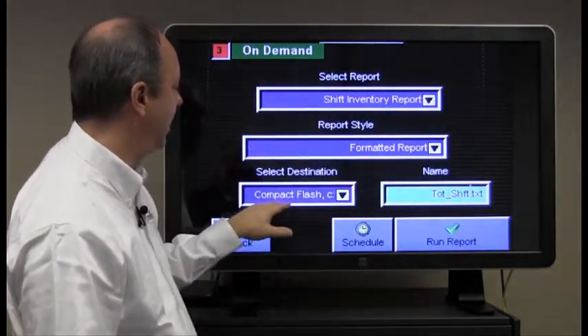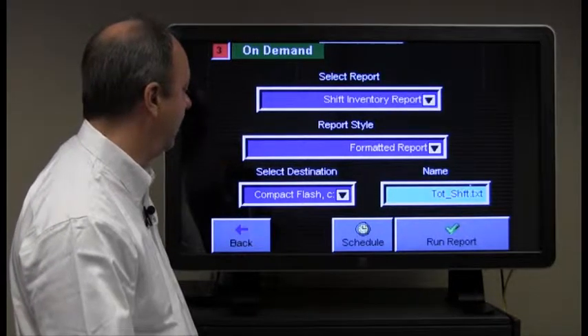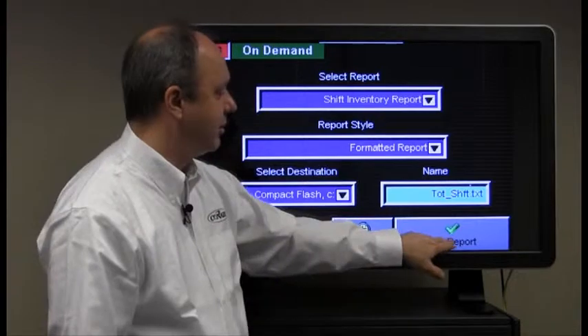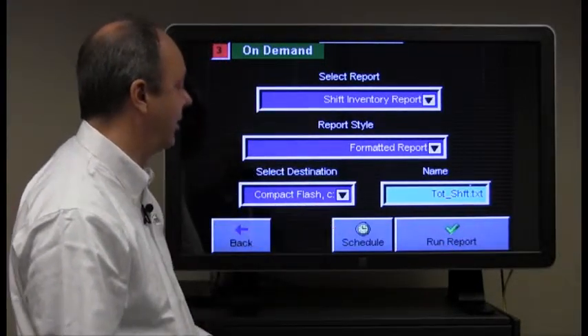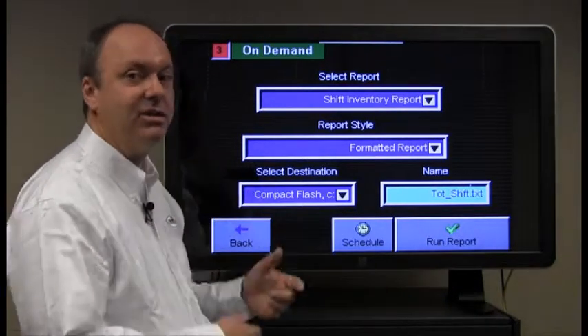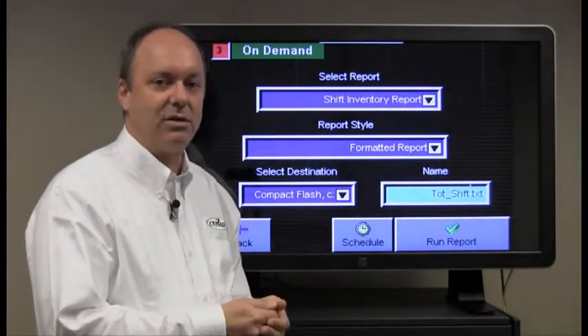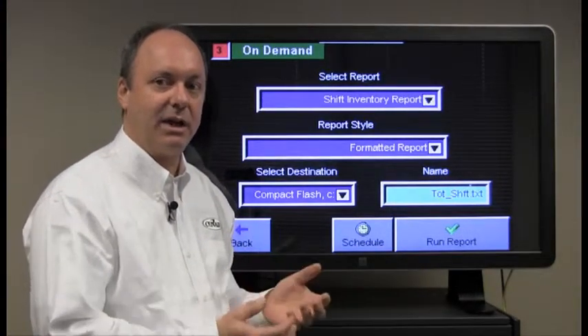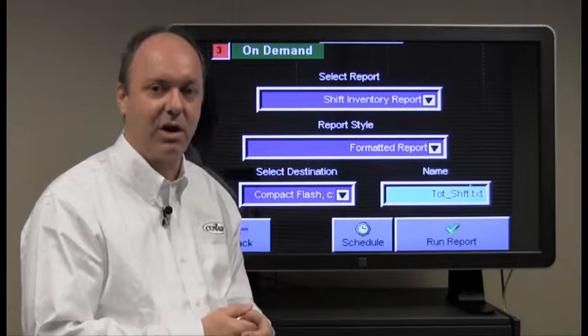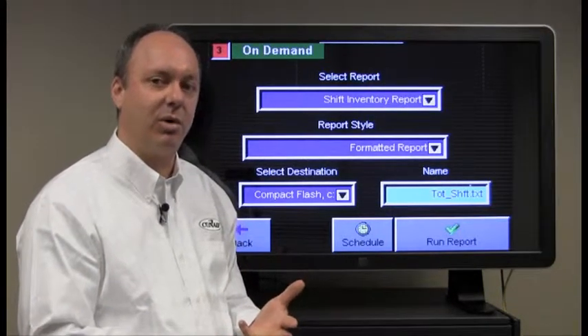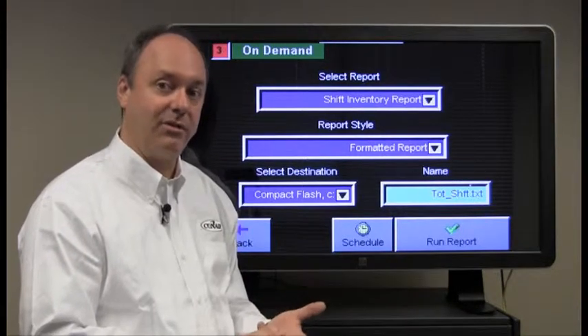So we have the report we want, the style we want and the destination as well as the name. The operator at this point would simply press run report and it would write the report out to the compact flash card. Now since the compact flash card is the destination in this example, it would require that the user be able to get that off of the compact flash card using an Ethernet connection with what's referred to as a file transfer protocol program or an FTP connection.